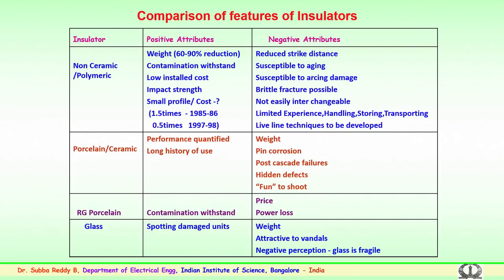Now some negative attributes: reduced strike distance, but this is again taken into consideration in the newer technologies. These are susceptible to aging. As I told, because of being organic in nature, polymer or composite insulators are susceptible to aging and degradation, the surface becoming brittle and stiff, hydrophobicity loss, and there could be a fracture, the material becoming brittle over a period of time. A lot of effort has been made toward material improvement. And as the technology is not very old, there is limited experience, particularly in handling, storing and transportation.